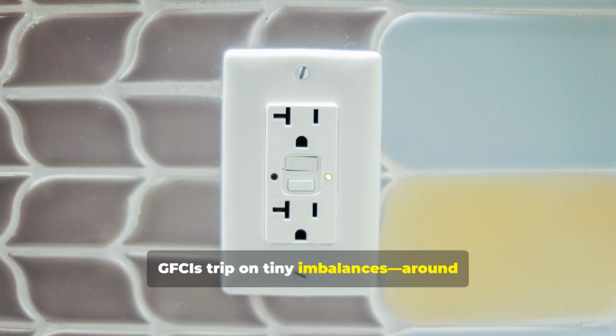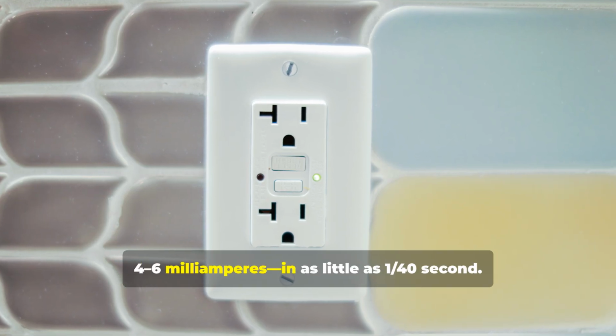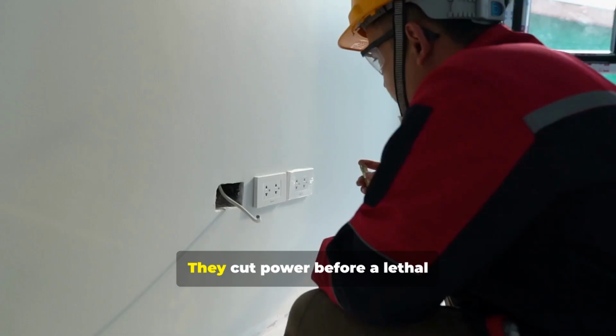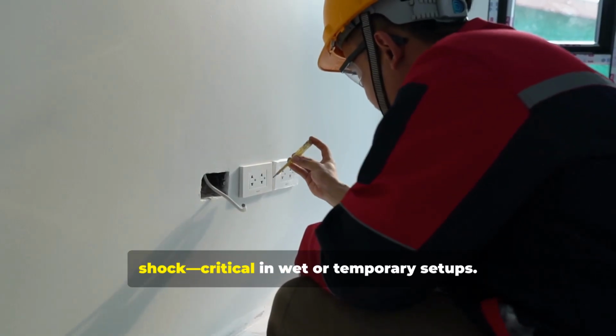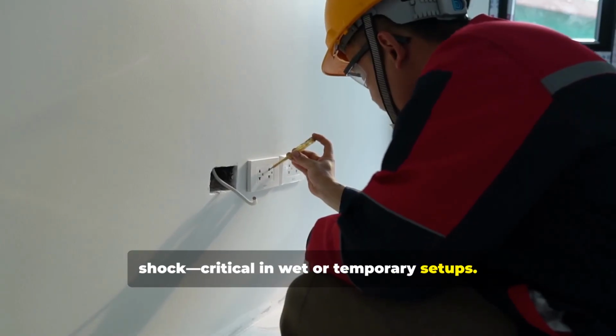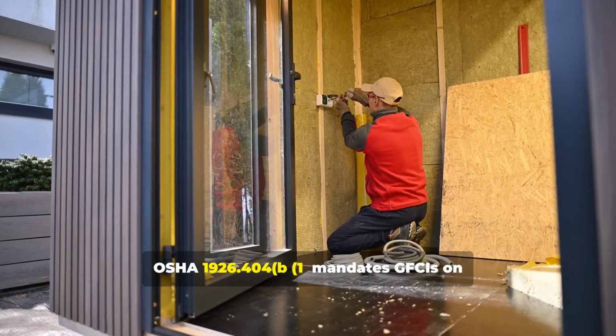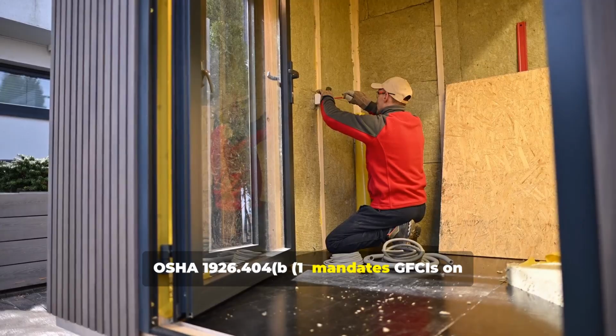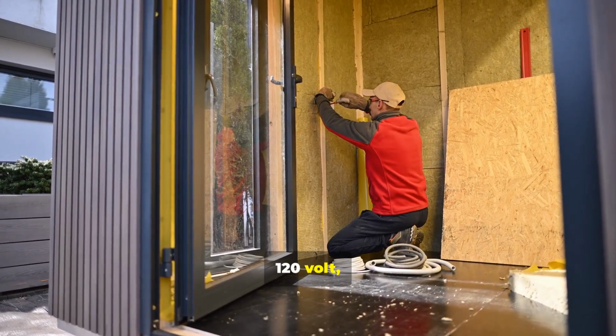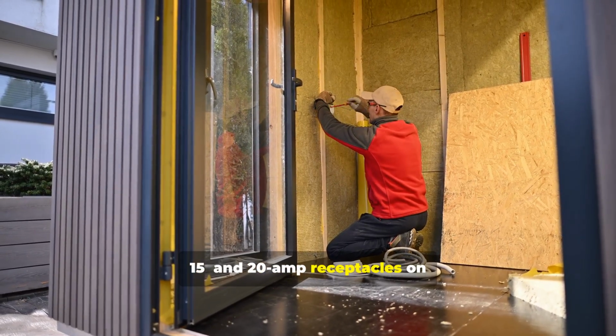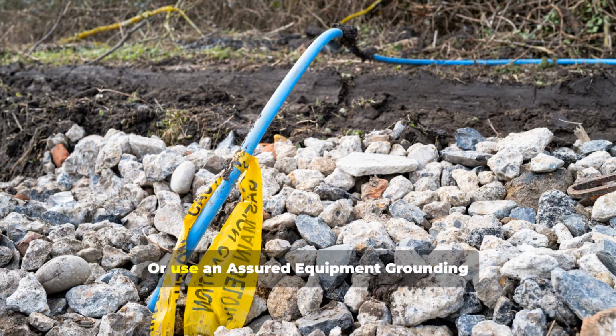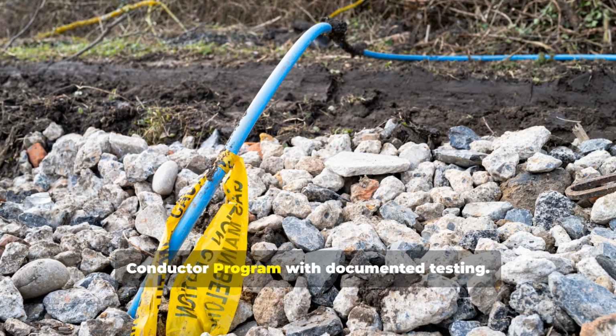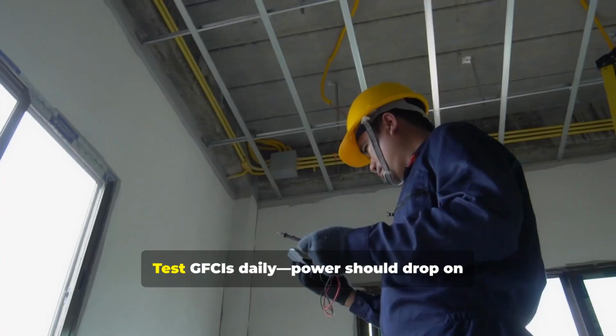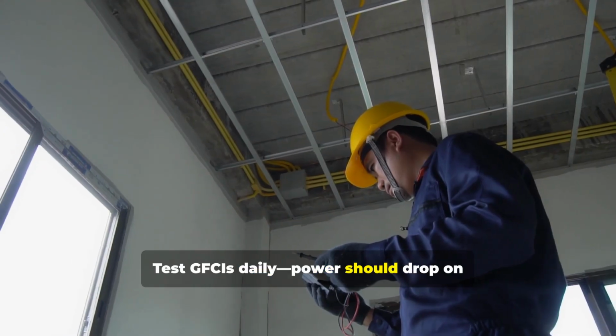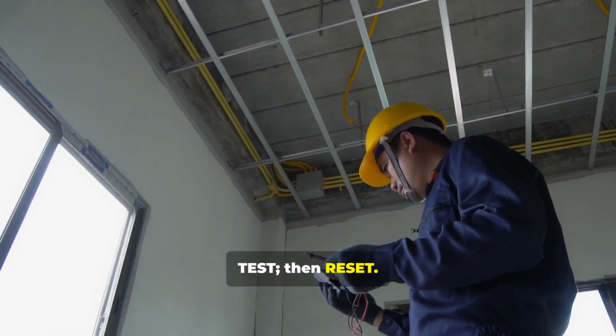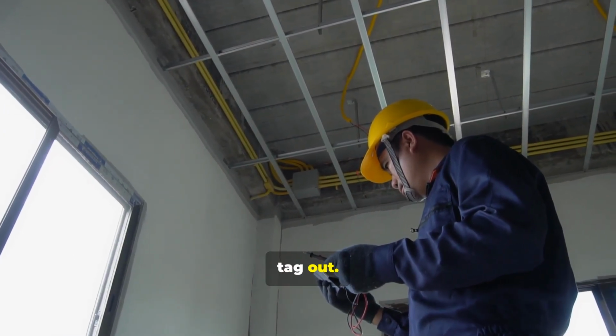GFCIs trip on tiny imbalances, around 4-6 milliamperes, in as little as 1/42nd of a second. They cut power before a lethal shock, critical in wet or temporary setups. OSHA 1926.404(b)(1) mandates GFCIs on 120-volt, 15 and 20-amp receptacles on construction sites, or use an assured equipment grounding conductor program with documented testing. Test GFCIs daily, power should drop on test, then reset. If it won't trip, tag out.